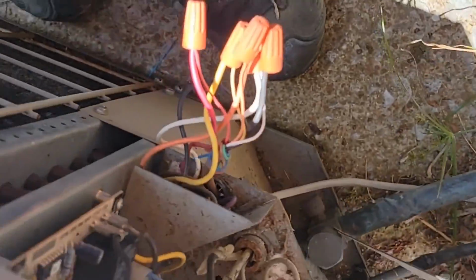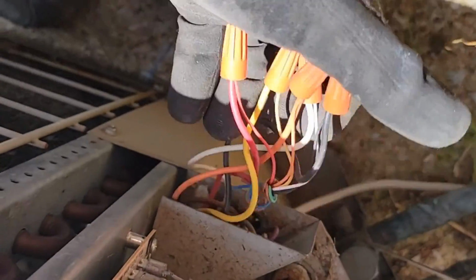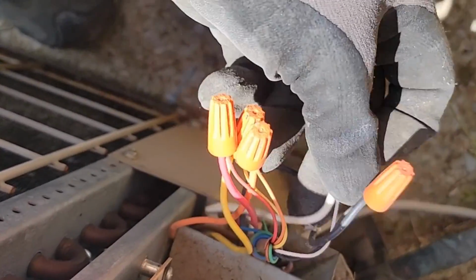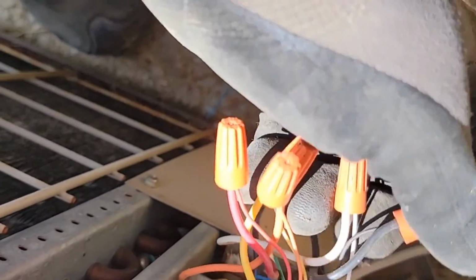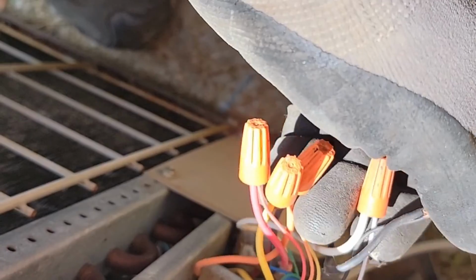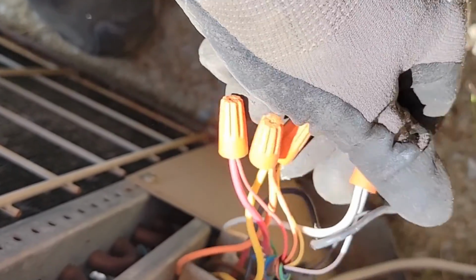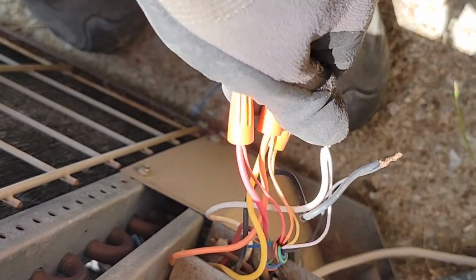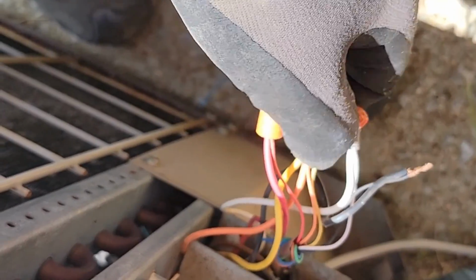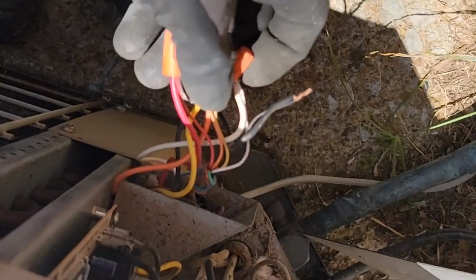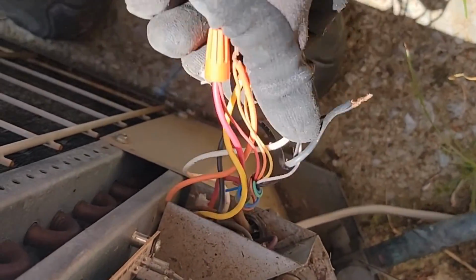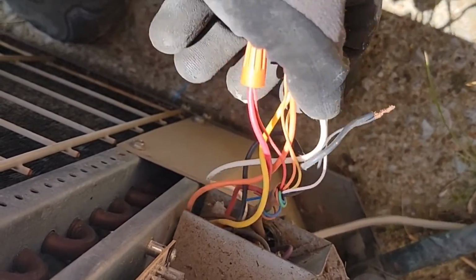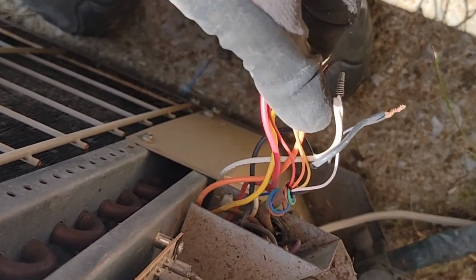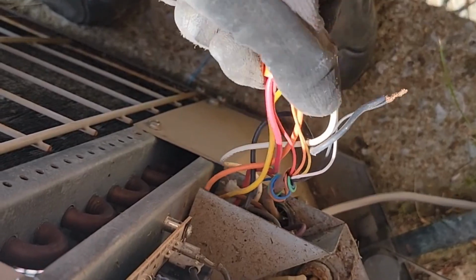Found another splice right here. Anytime you got a fuse blown, transformer blown, you put the new transformer in, you need to do a process of elimination. So I can take the wires off out here, put the fuse back in, see if the fuse blows. If it doesn't blow, then I know it's inside the condenser. Okay, if it does blow, then I know that it's not in the condenser.